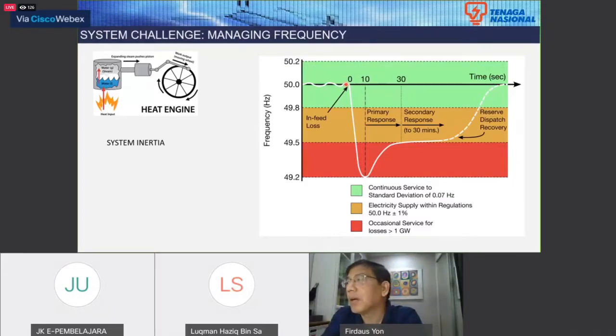So we have systems in place to clear a fault—essentially sectionalizing the affected areas—and after that the system recovers. Now, what we have in our system is a collection of rotating machines, all rotating at the same speed, basically at the same frequency, generating electricity at about 50 hertz.